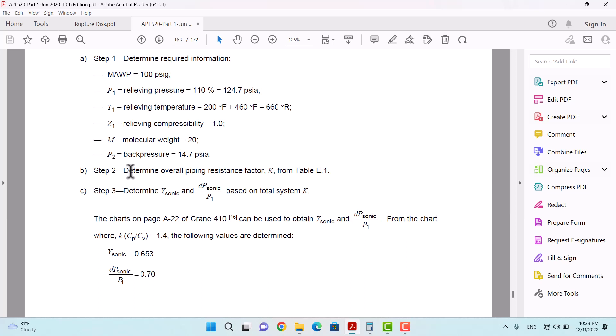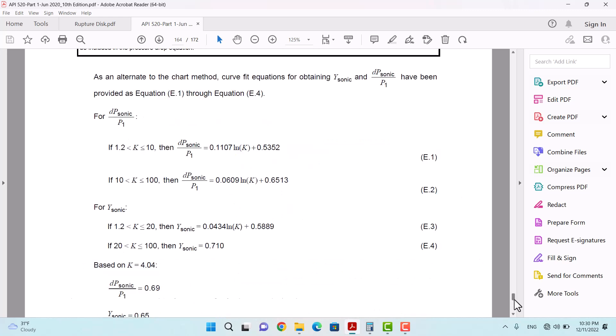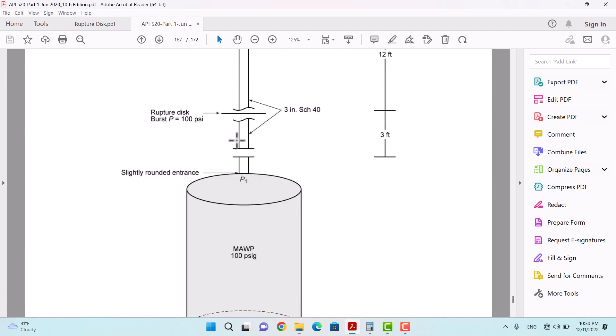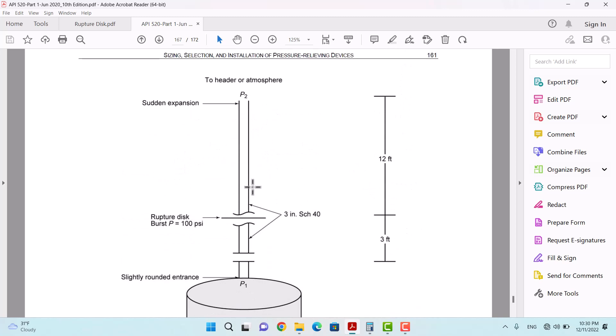In the second step, we determine the overall piping resistance factor. We create a table and calculate the total system K-value, dividing it into different sections: the sharp edge entrance, the K-value for the rupture disk, the K-value for the 15-foot distance between the rupture disk and the outlet point, the sudden expansion, and we sum all of these. We consider a K-factor for this inlet length, for this distance, for the rupture disk itself, and for the sudden expansion.